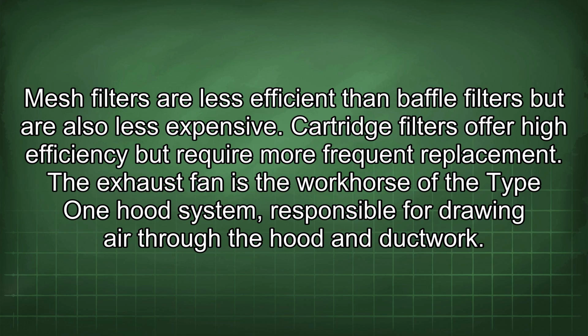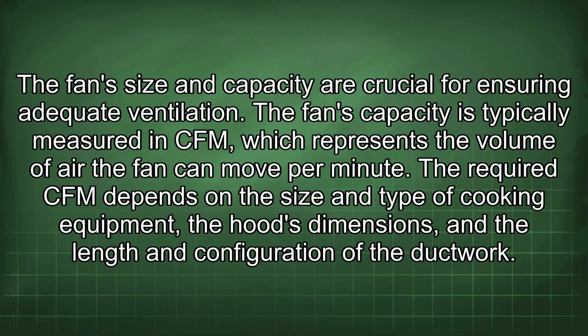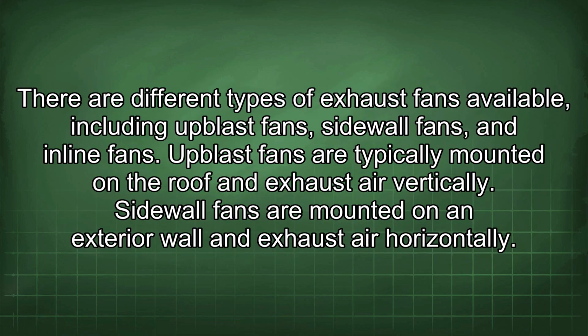The exhaust fan is the workhorse of the Type 1 hood system, responsible for drawing air through the hood and ductwork. The fan's size and capacity are crucial for ensuring adequate ventilation. The fan's capacity is typically measured in CFM, which represents the volume of air the fan can move per minute. The required CFM depends on the size and type of cooking equipment, the hood's dimensions, and the length and configuration of the ductwork. There are different types of exhaust fans available, including upblast fans, sidewall fans, and inline fans.